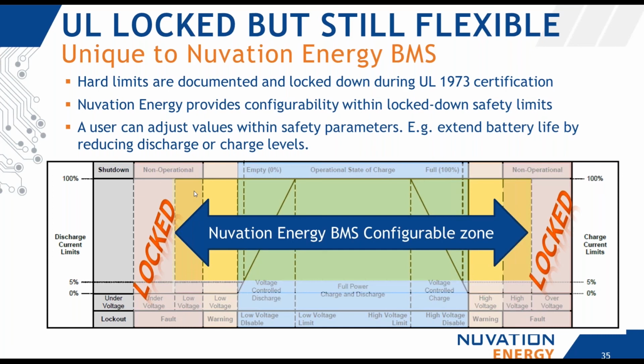And so by allowing those limits to be configured, the BMS can send messages out to the high level system and stop itself from getting discharged below what the PCS can do, even though that's not related to the absolute minimum value that the cell supports. This is also useful when we talk about the depth of discharge and minimizing or adjusting the range, so that way you can extend the life of a system.